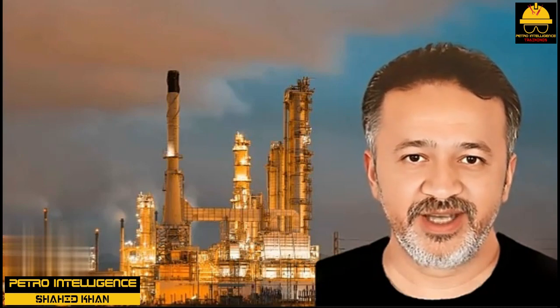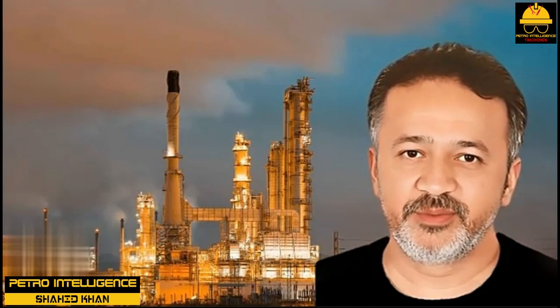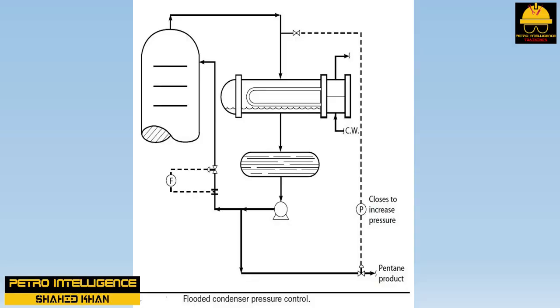How do we know what pressure target to select? Let us have a look at this pentane-hexane splitter. The tower simply could not make a decent split, regardless of the feed or reflux rate selected. The tower top pressure was swinging between 12 and 20 psig. The flooded condenser pressure control valve is operating between 5 and 15% open, and hence it is responding in a non-linear fashion. Most control valves work properly only at 20 to 75% open.